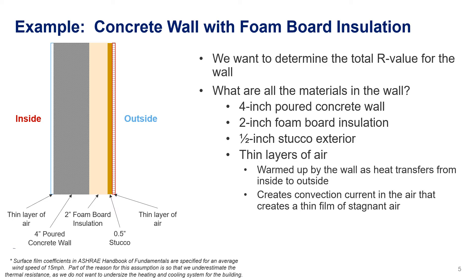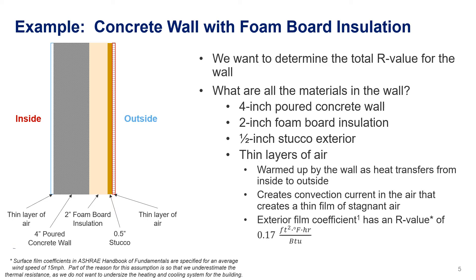Another factor that plays a part is wind. When wind hits that wall, it moves the air away from it and reduces the amount of resistance we have. So experimentally, it has been determined that the thermal resistance value on the outside for most normal applications is 0.17 square feet, degrees Fahrenheit, hour per BTU. This is called the exterior surface film coefficient, or exterior film coefficient for short.